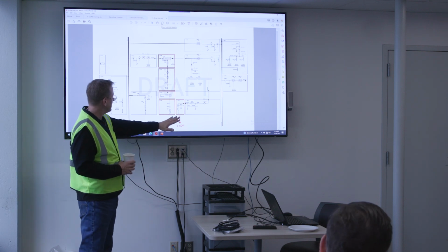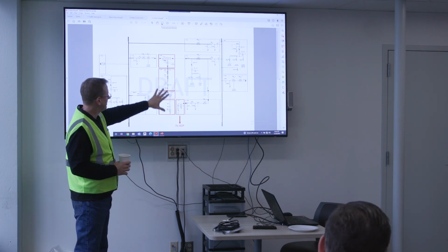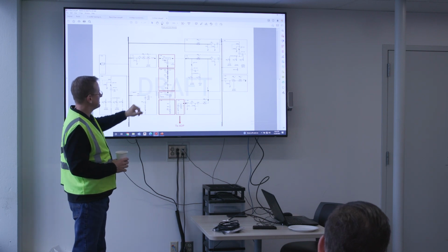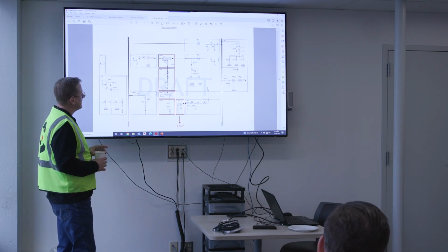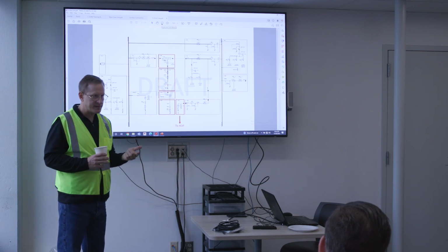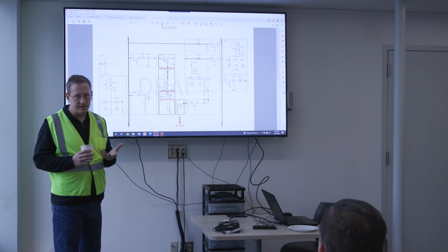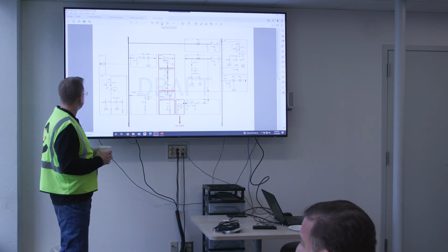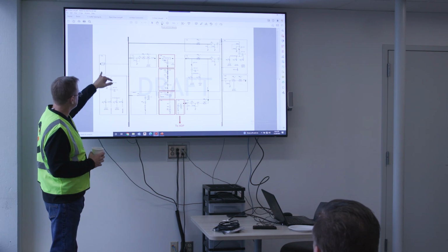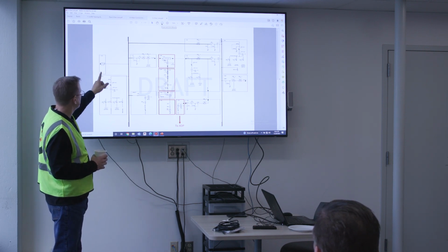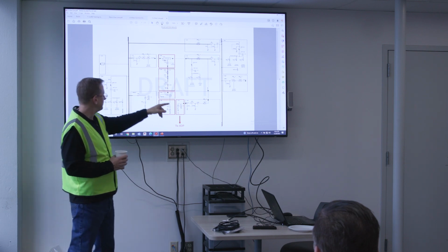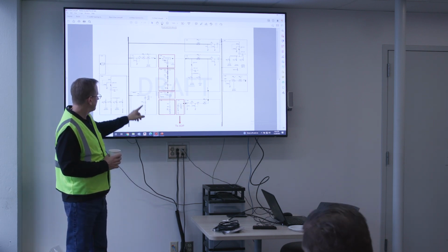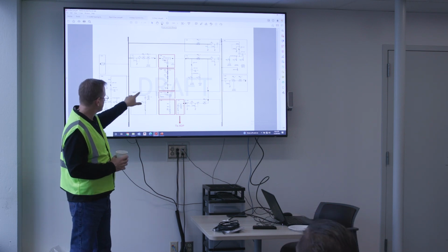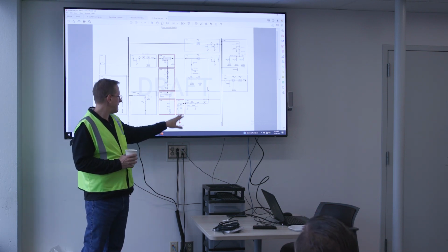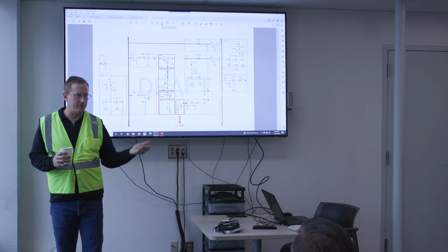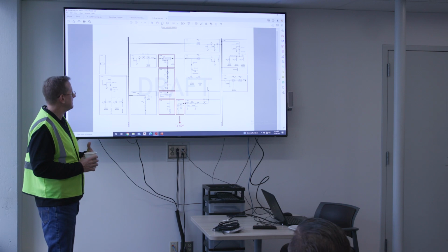Okay, so again, everything in red is an external panel, and everything else is part of the medium voltage gear. You also have control panels that were delivered with the Hitec system. The UCP, for example, is our main control panel, and it has feeds coming to it from sensing going to the dicon, from the input and the output, and it's got power that comes to it through both the main side, through this transformer, and through the utility side, through the ADP as well. So it has both utility and critical feeds coming into the UCP.